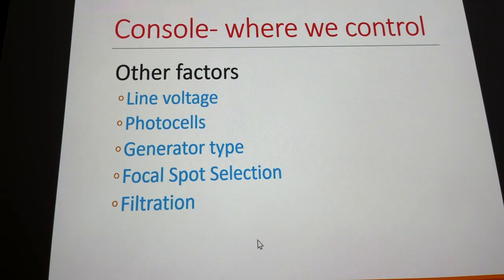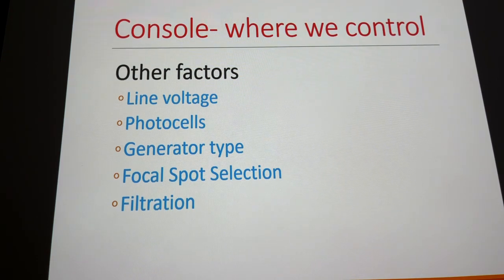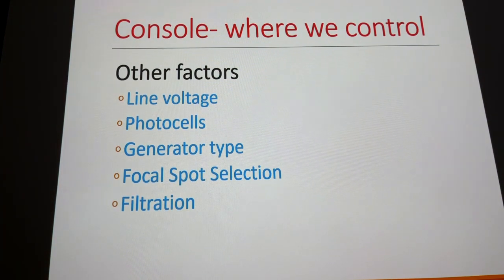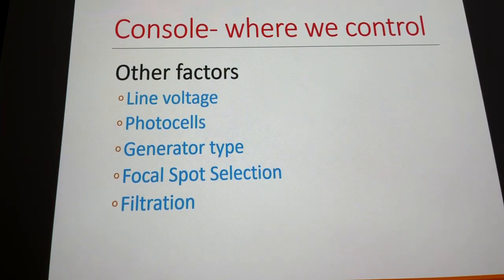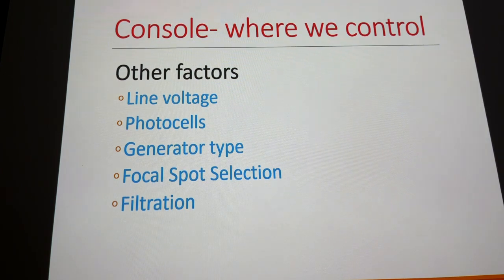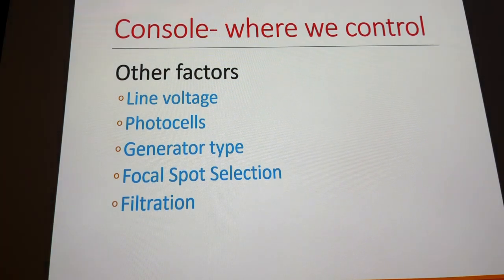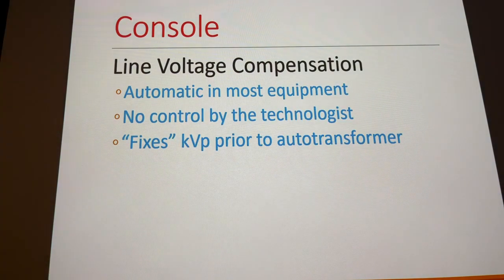Other things we have to consider, even if we don't directly manipulate them, include line voltage compensation, photocell selectors, and generator type — which is set by the machine type we use, not adjustable from the console. Focal spot selection we do control, and filtration in as much as we might use compensating filters to affect a change.